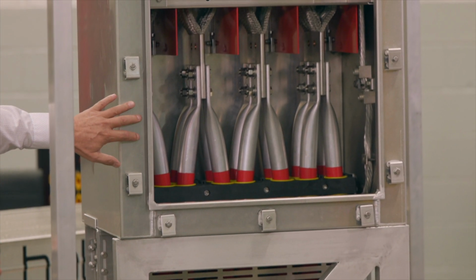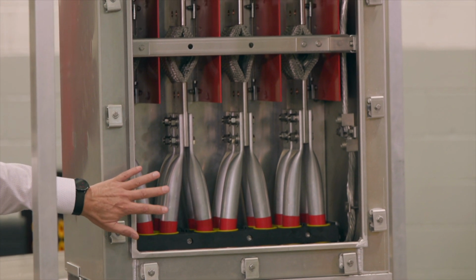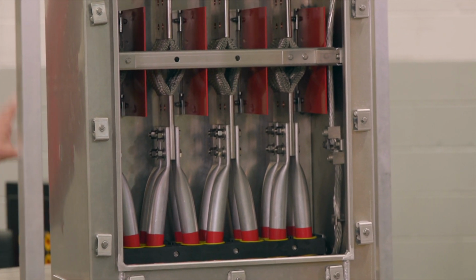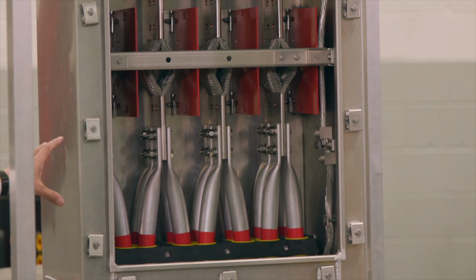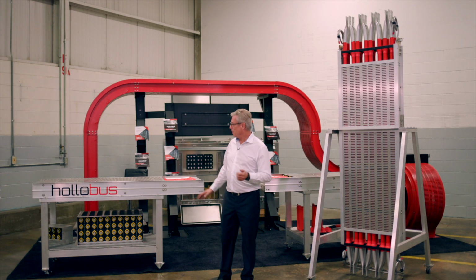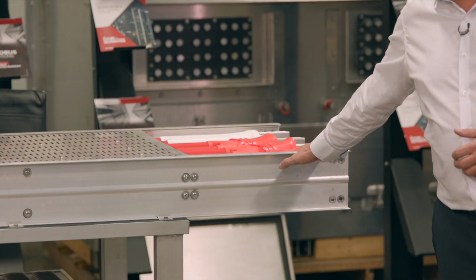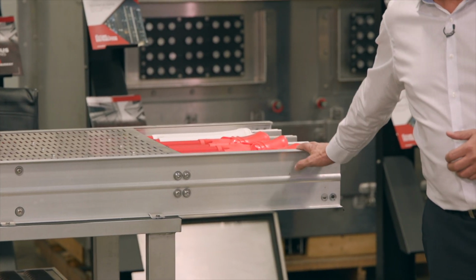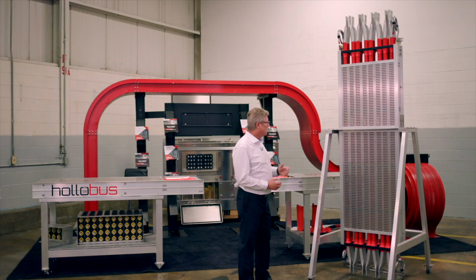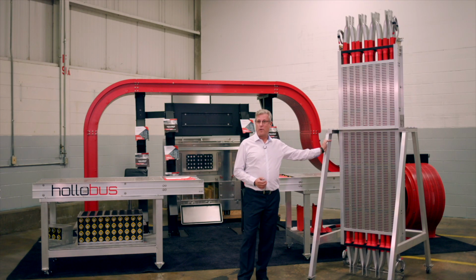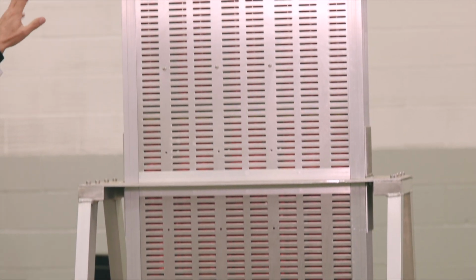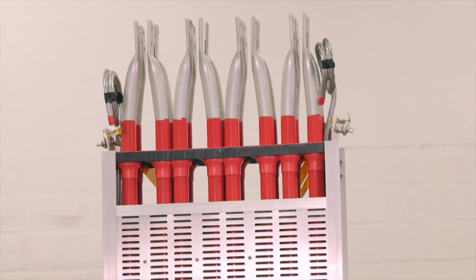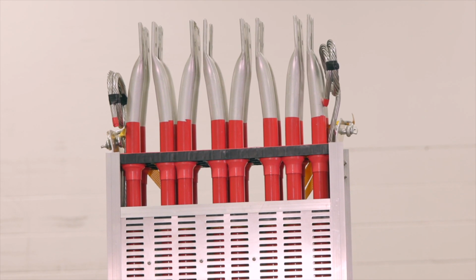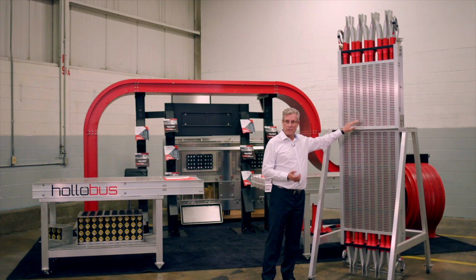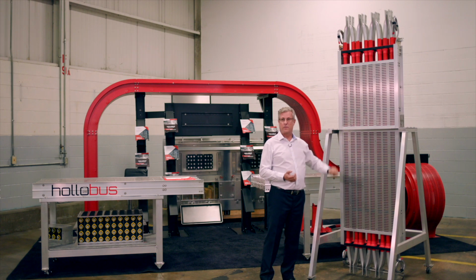Once this plate is on and this enclosure is tight, you could essentially flood this floor. This Hollobus will not be affected. It will not fail. Behind me, you'll see a horizontal system, which is available up to 45-foot long sections, self-supporting. We also have vertical systems that can go up high-rise buildings. Where the grounds come out, you'll notice on the side we've got lifting pads and lifting joints for this to be lifted up and dropped into place through the building floor. This would get bolted down. This system is finished at that point and ready to be connected to the system on the next floor itself.